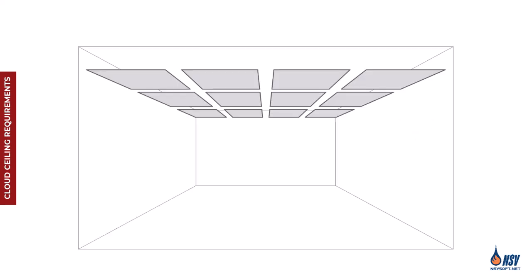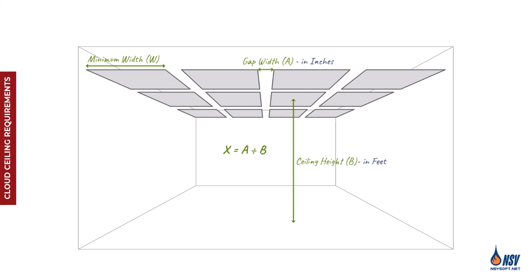In this table, the maximum sprinkler protection area is determined by two key factors: the minimum width of the ceiling panels and the ratio of the gap width to ceiling height. It's important to note that this ratio must be calculated using inches for the gap and feet for the ceiling height.